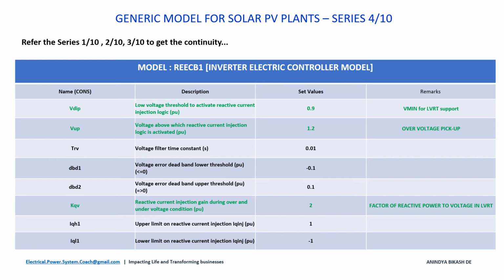So the first one, VDIP, it is the low voltage threshold to activate reactive current injection logic. So basically this is the point from where LVRT mode starts. It depends on the various grid codes. Suppose in one grid code the continuous operation is specified for any inverter from -10%, then in that case we can set the VDIP as 0.9. So up to 0.9 per unit voltage at the inverter terminal, there will be no reactive power support, but whenever the terminal voltage goes down below 0.9, in that case this inverter will go into LVRT mode.